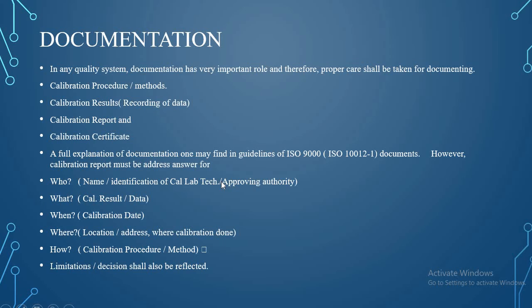Now the last but not least is the documentation. When we do the calibration of any equipment or instrument, documentation is a very important part. In any quality system, documentation has a very important role, and therefore proper care shall be taken for documenting. So in documentation, we have to mention the calibration procedure or methods followed during the calibration of the particular equipment or instrument. Then we have to mention the calibration results also, that is the recorded data.